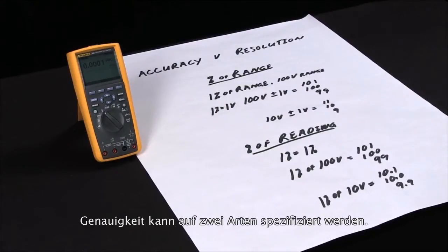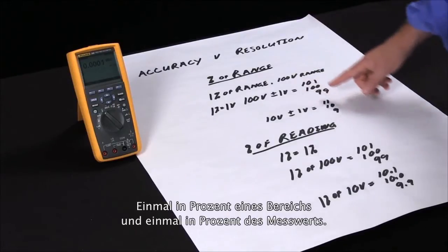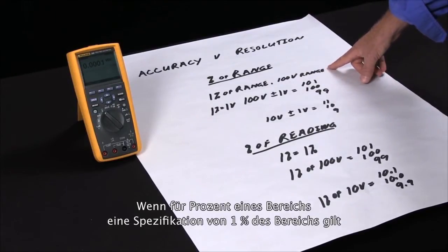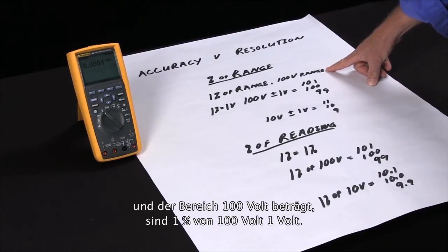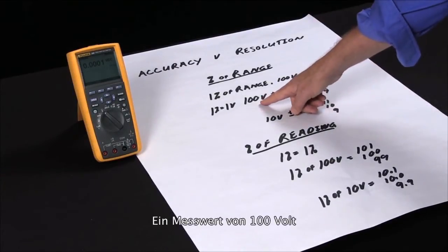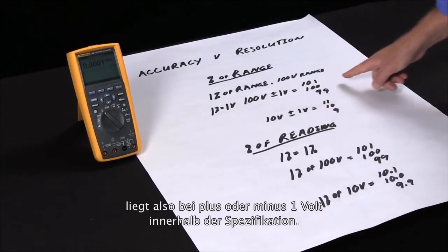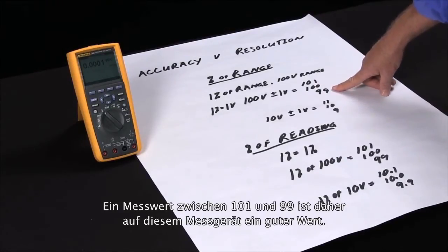There are two ways accuracy is specified: percent of range and percent of reading. For percent of range, if we have a one percent specification of range and we're on a hundred volt range, one percent of a hundred volts is one volt. So with a reading of a hundred volts, the reading can be within specification at plus or minus one volt — a reading between one hundred one and ninety nine is actually a good reading on this meter.